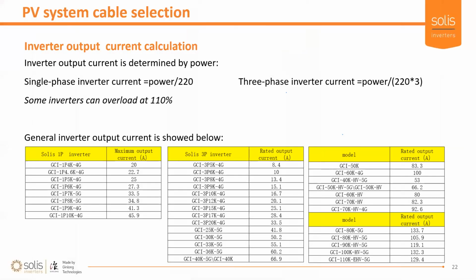So yeah, as I said, when designing the AC cabling for a system, the first parameter you need to find is the maximum current that will be put through that cable. The formula for current is the power going through the cable divided by the voltage on that cable. Single phase systems are easier because all the power is running over that single phase. However, not that much more complicated in three-phase systems. You just need to divide the total power by 3 to get the per phase power.